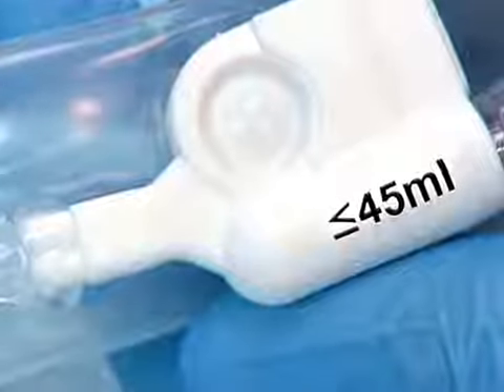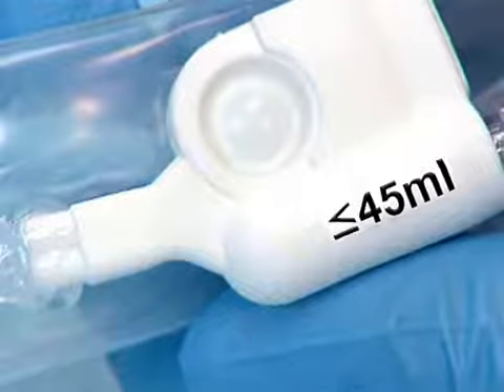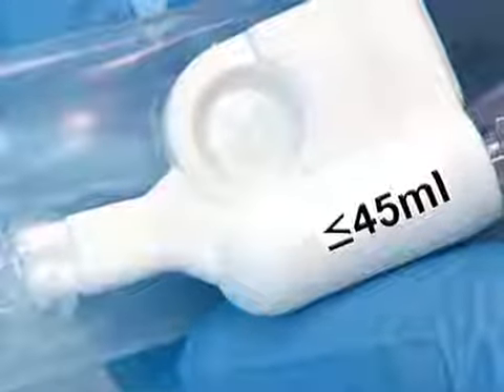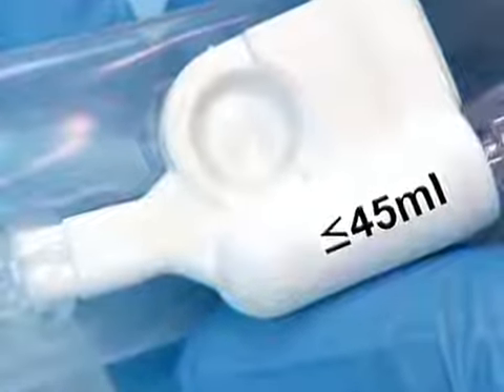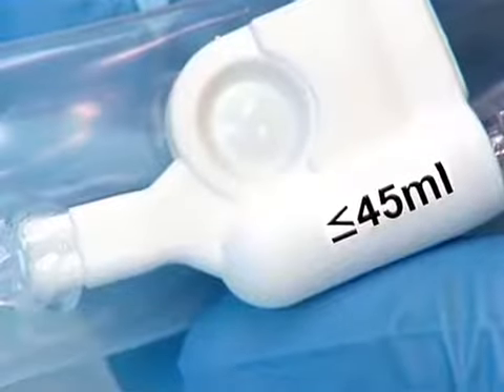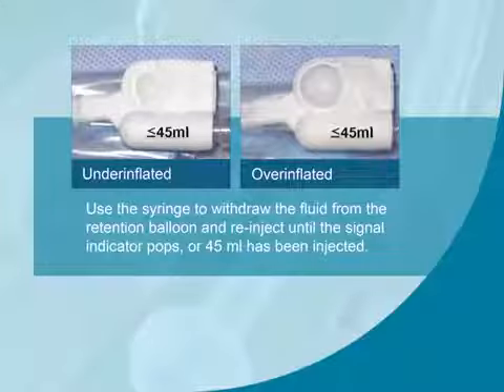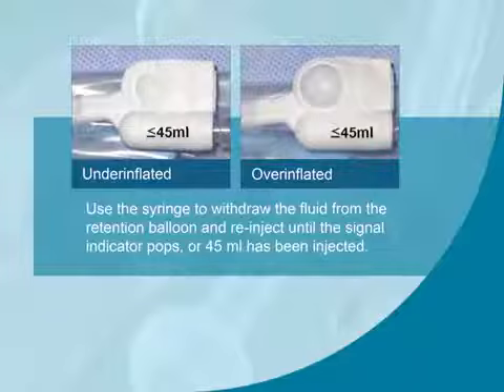Should the indicator deflate or appear excessively inflated after proper inflation, this is an indication that the retention balloon is no longer at the optimal fill level. In this case, use the syringe to withdraw the fluid from the retention balloon and re-inject until the indicator pops or 45 milliliters has been injected.